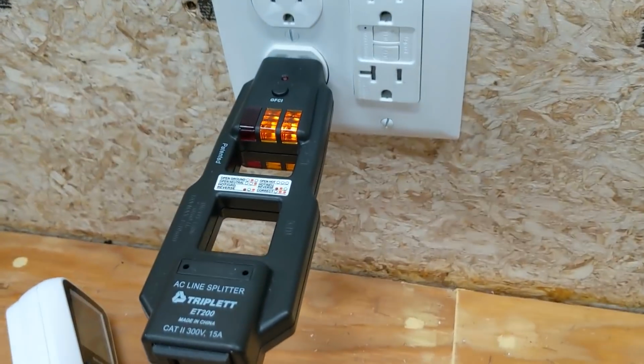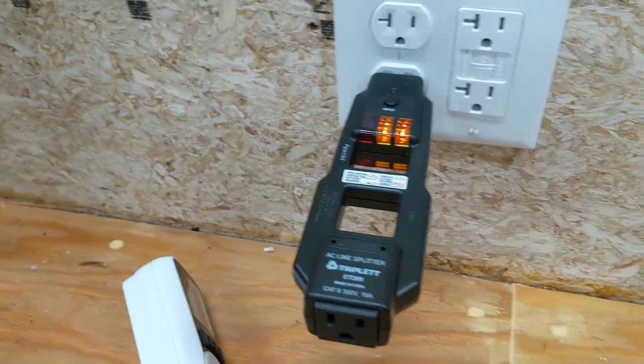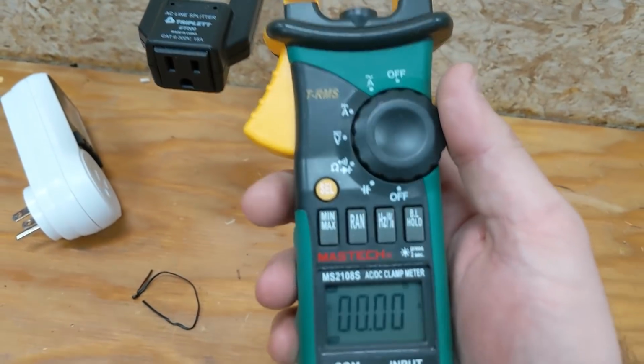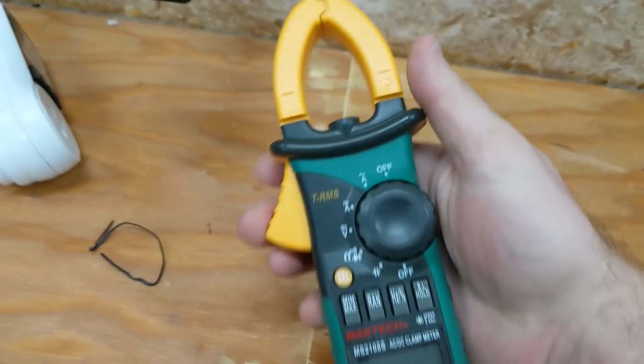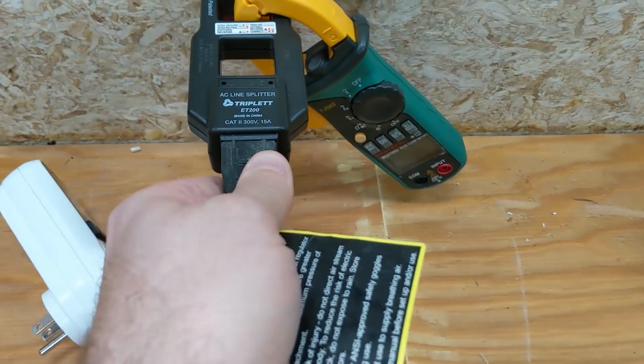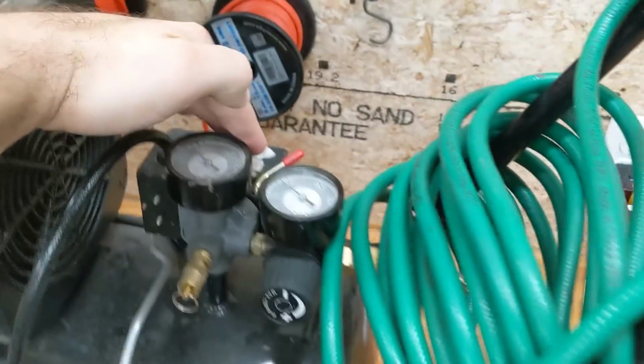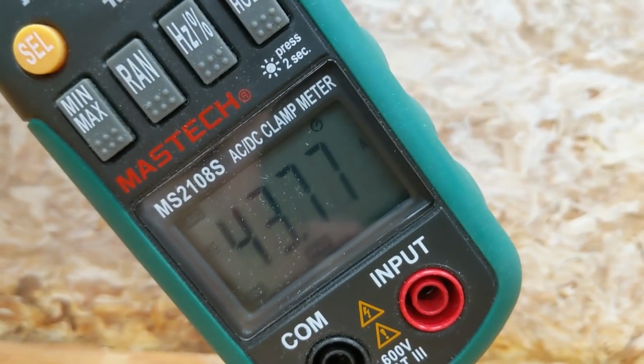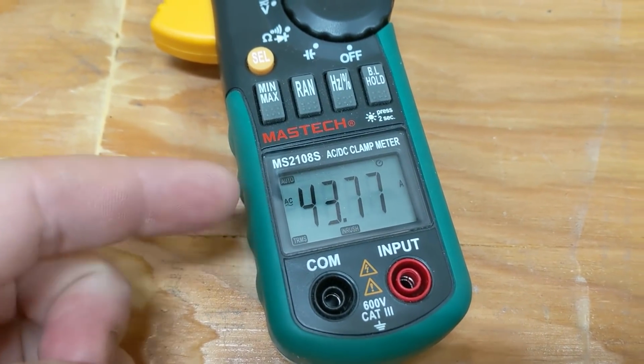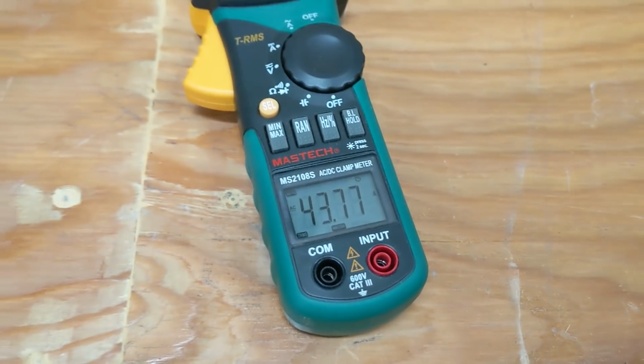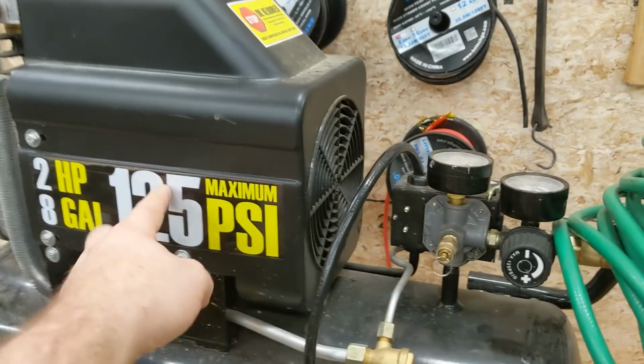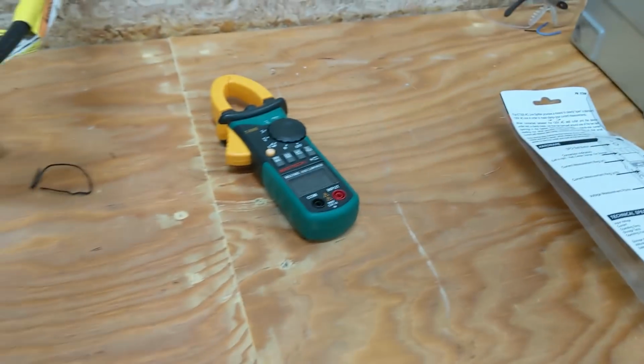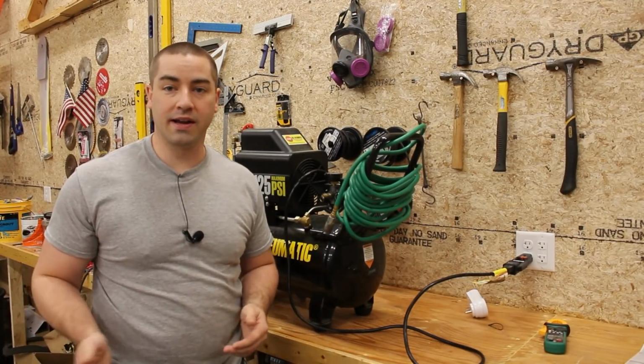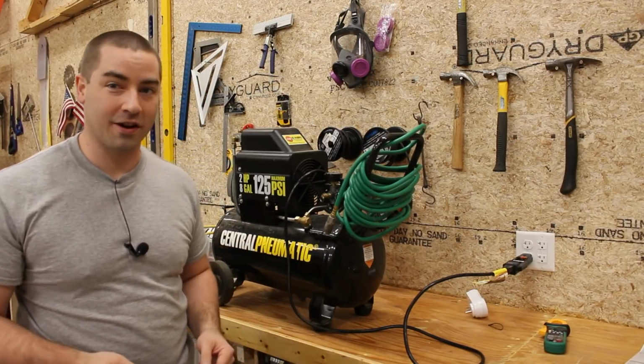To find out the surge rating, we're going to use this tool. I'll set this meter to inrush, so it'll hold that, plug in the air compressor, and turn it on. Our inrush was 43.77 amps, so almost 44 amps. We know it's a 14 amp motor while running, but it pulls 44 amps during inrush. We now know the Bluetti cannot do 44 amps at inrush.